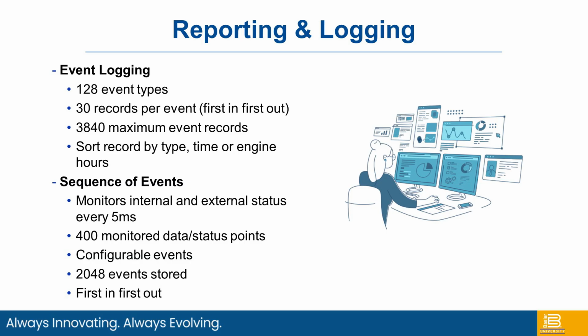There's also a sequence of events, which monitors internal and external status every 5 milliseconds. There are 400 monitor data set points, status points, and configurable events. So you can configure this sequence of events to start recording when a certain event happens. Like if you happen to hit over voltage, you could set it so that it records after it hits the over voltage, and there are 2,048 events that are stored first in, first out as well.